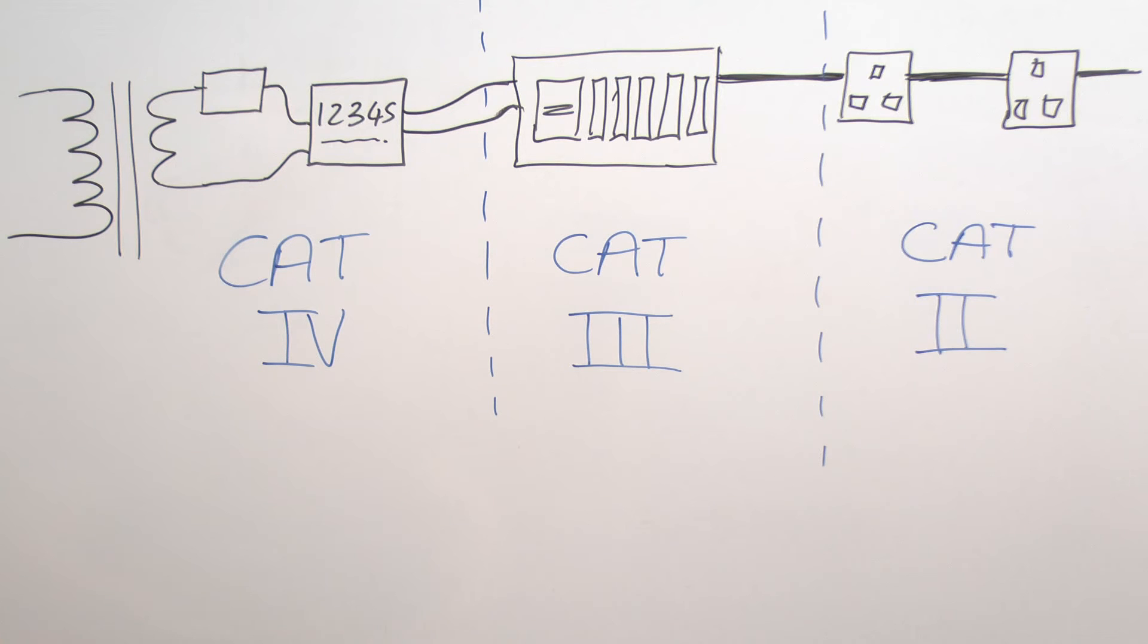And the other point as well is that certainly at this kind of level at the category 4 areas where you've got a substantial amount of fault energy available, it's all very well using the proper test equipment and probes. But certainly here you ought to be wearing protective clothing as well because in the event of some kind of fault you certainly don't want to be exposed to burning metal and large amounts of arc energy. And if you have a look at that video linked in the description you'll see why that's actually important. So face shield and flame proof clothing really are essential when working in this kind of area.